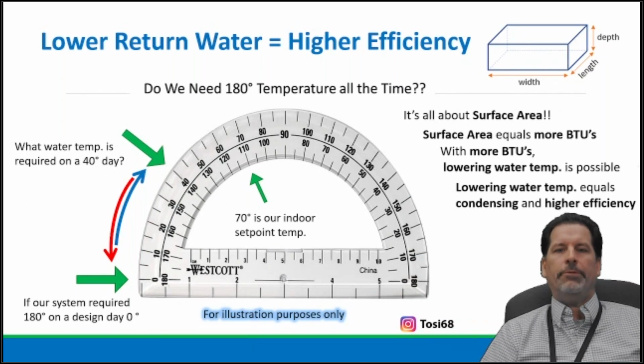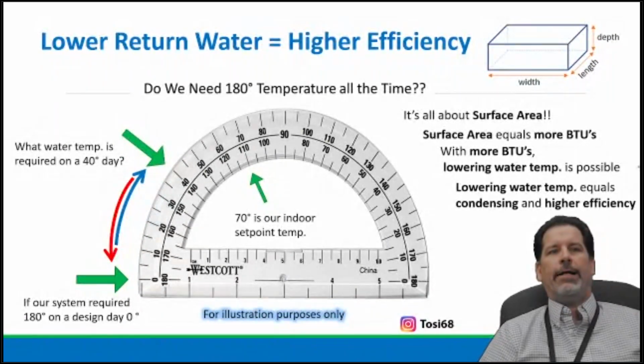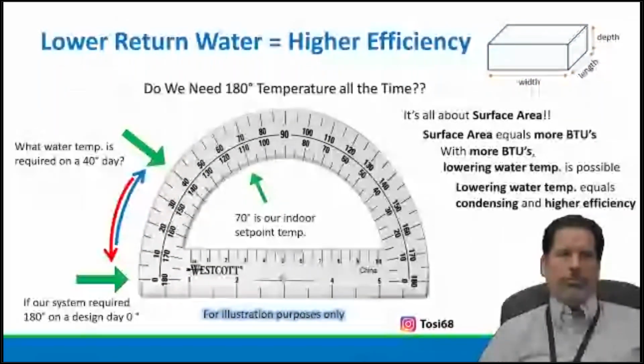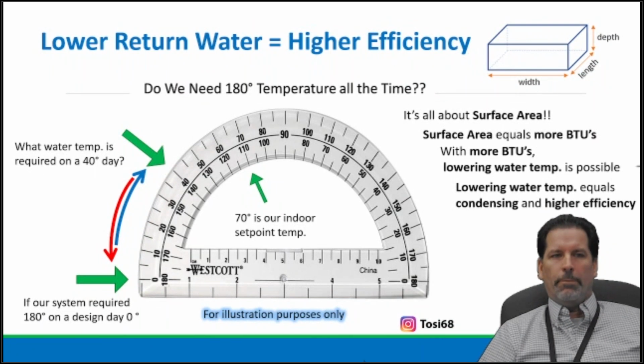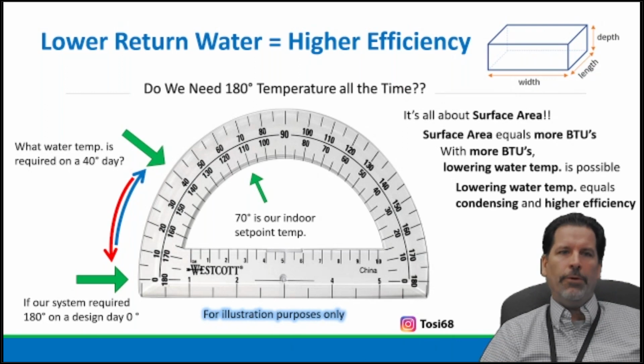But as it's warming up during the day, even if it's 25 out, sounds cold but it's warmer than 0, do we still need to deliver 180-degree water? The answer is no. We're sizing our emitters, baseboard, hydrocoils, radiant, panel rads, whatever it is that's in the home or your choice of install, based off of a worst design condition, whether for heating in winter or cooling in the summer. And if we achieve that pinnacle, that very point, then the rest of the season we could be something less. So we have modulation.